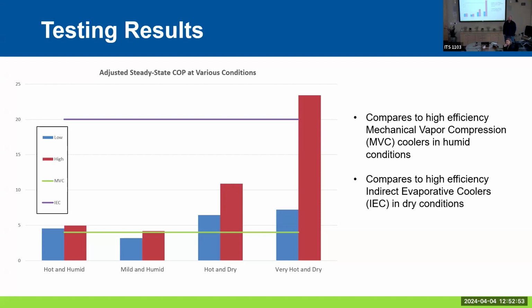Is that room cooling capacity, or is that capacity cooling outside air down, like the mixed air capacity? I did both, and I don't remember what I'm showing here. They're both relevant. Yeah, I would assume this is the mixed air capacity, because we need different ones for the various mixed airs. Right. If it was just room, there would only be 4 values here instead of 8. Well, if it were just room, there's ventilation air. Yeah, but this would be the total COP, not just the room COP.